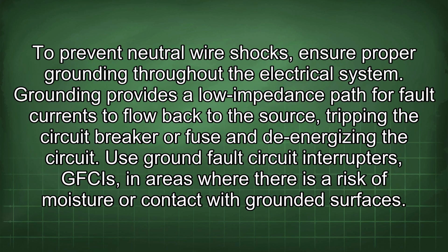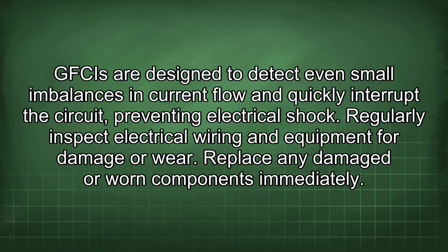To prevent neutral wire shocks, ensure proper grounding throughout the electrical system. Grounding provides a lower impedance path for fault currents to flow back to the source, tripping the circuit breaker or fuse and de-energizing the circuit. Use ground fault circuit interrupters, GFCIs, in areas where there is a risk of moisture or contact with grounded surfaces. GFCIs are designed to detect even small imbalances in current flow and quickly interrupt the circuit, preventing an electrical shock.